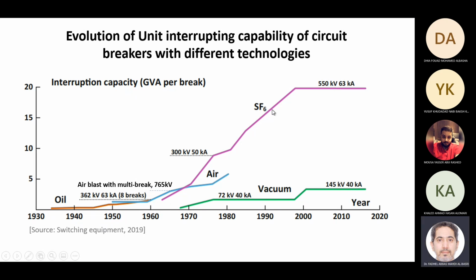For SF6, which is gas circuit breakers, they have higher breaking capacity. That's why they can be used at high voltage systems. They have high breaking capacity and can be used for high voltage systems and extra high voltage systems. So most of the breakers now at the high voltage systems are SF6.